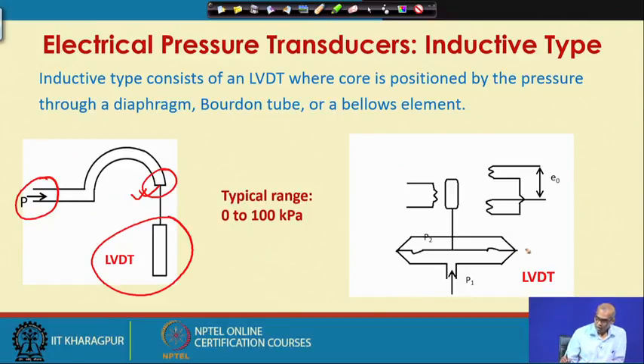Similarly, I have this diaphragm. When I apply pressure here, this diaphragm deflects. Now, this core of LVDT is attached to the diaphragm. So, as the core shows displacement, the output voltage will be a measure of the displacement of the core, which in turn is a displacement of the diaphragm, which in turn is a measure of pressure.